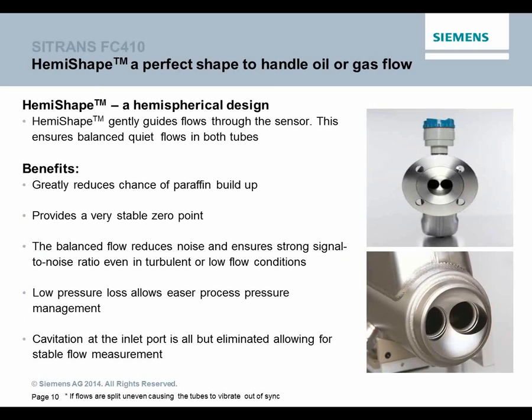One of the other benefits that has come up is, since this is a dual tube meter, meaning there are 2 inlet ports within this device. If it's a 1/2-inch meter, there are 2 1/4-inch meters. This Hemi-shaped inlet port, yes, it has a Hemi in it, helps keep the process quiet. It was originally designed in order to allow for a 3A sanitary approval, but what they found is that when they were doing that, they had no dead zones for anything to hang out, and it created an extremely quiet flow profile. That extremely quiet flow profile aided in a very, very good signal-to-noise ratio.